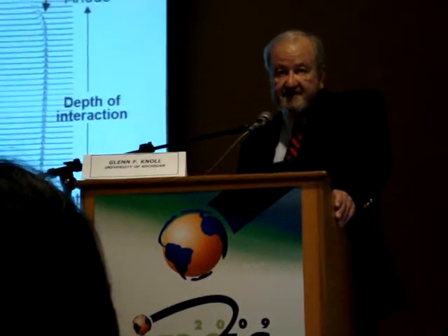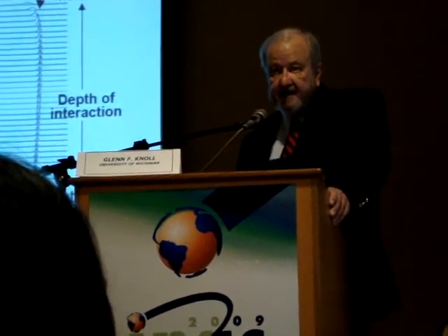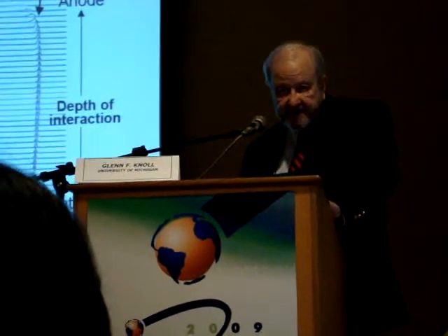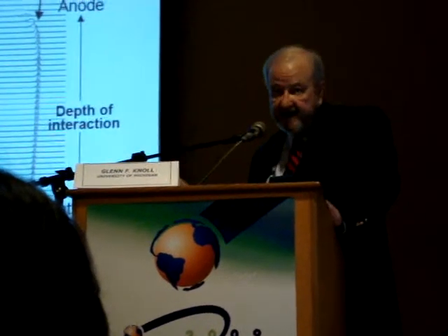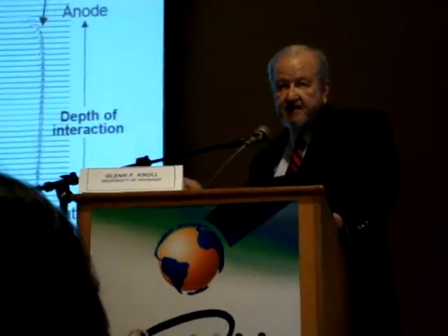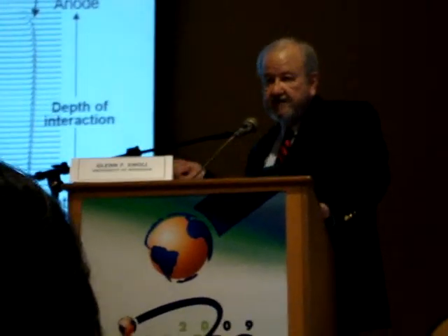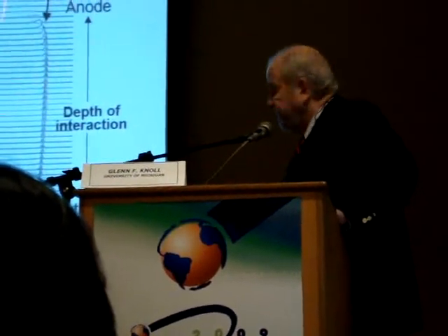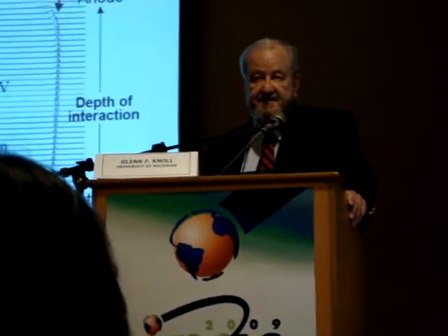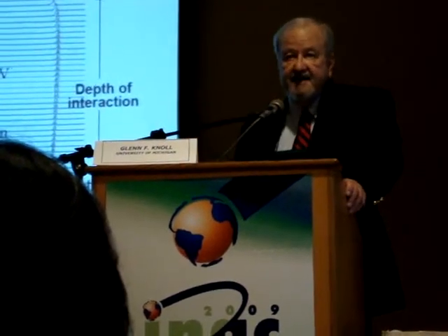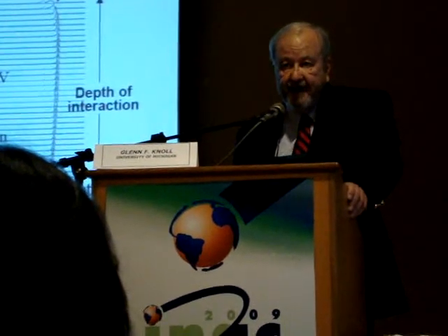Well, there's obviously now a way to fix this electronically, because now you have separately the pulse height spectra at each different depth. This is stable behavior. It does not change dramatically over long periods of time. So it can be calibrated. So an initial calibration can tell you how much of the signal is missing because of the charge trap, and that can be added back in electronically to compensate for the trapping.